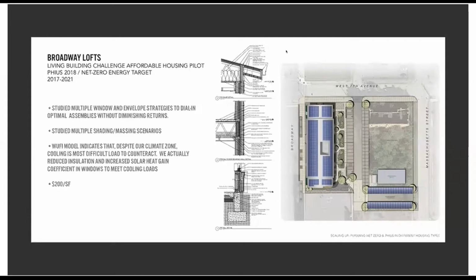One interesting thing we found during design was that even though the building is in a northern climate, just because of the orientation and scale of the building, we were having the most issues meeting the cooling load. So we ended up reducing the amount of insulation from where we started, and increased the solar heat gain coefficient on our windows to help counteract those cooling load issues. On the back of the napkin, if you do typical PHIUS assemblies, we found once we got into the details that we could dial that in a little closer and actually save money at the same time.